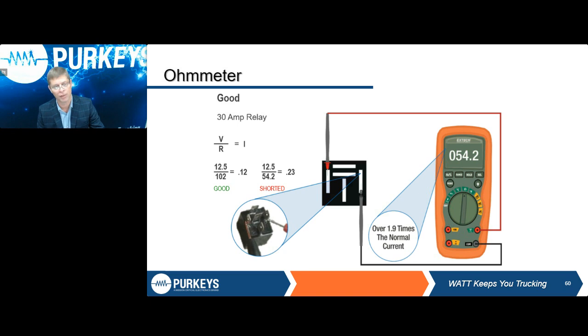That control module or HVAC module or SAM module, whatever controls this, it could damage it because you're pulling too much current through it, or it's going to shut down to protect itself. If you don't understand what it did, a lot of times the first reaction is, hey, I got a bad module. So I'm going to replace a $300 or a $1,000 module or whatever. What's actually wrong with this truck? A bad $3 relay. So it's not simply, does it click and work? We have to go through and actually do those checks.